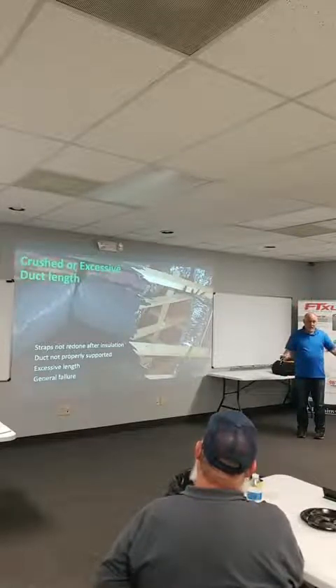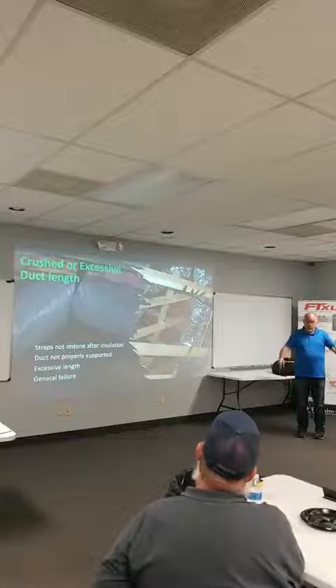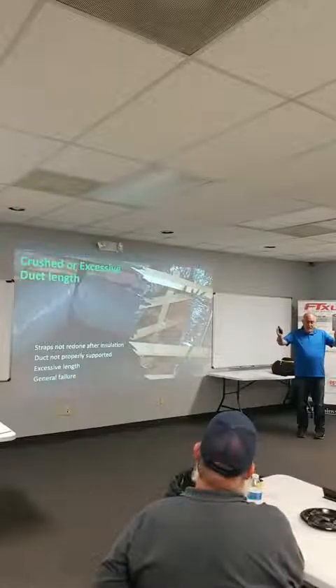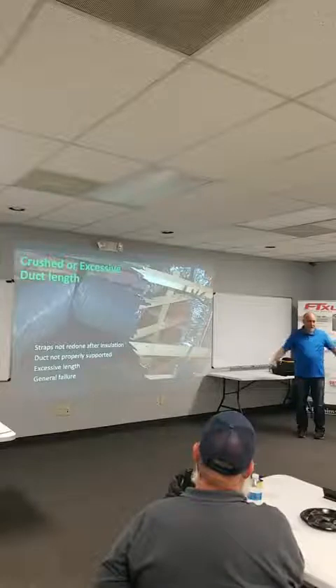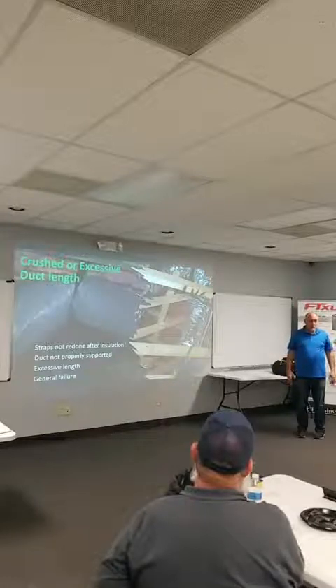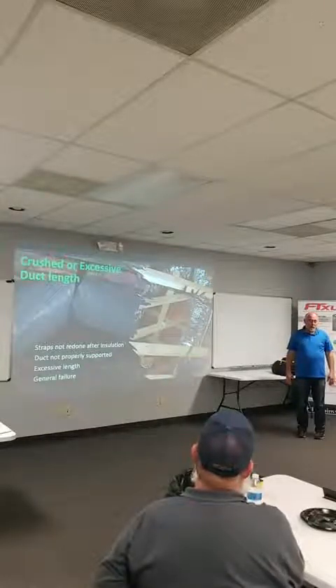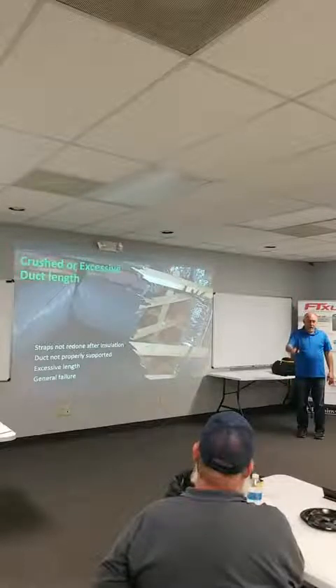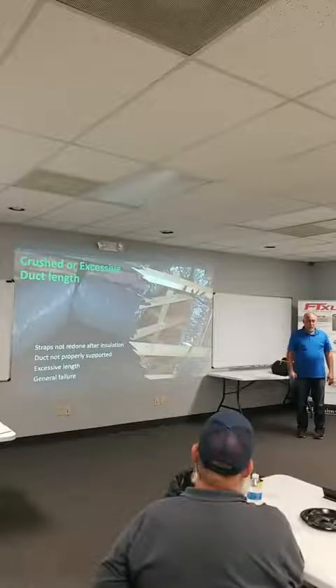This is the most common problem we see. I'm not kidding you, I went to a job in Texas, and every single run had 25-foot flex duct. And one run had the flex duct box open at this end, and opened at this end, and connected, because it was only about 6 foot long. His boss told him he did not want to see, there's 25 runs, 25 boxes of flex duct, I don't want to see any of this back at the shop, use it all. And then he told him that the system was proportional balancing if he kept all the runs the same.